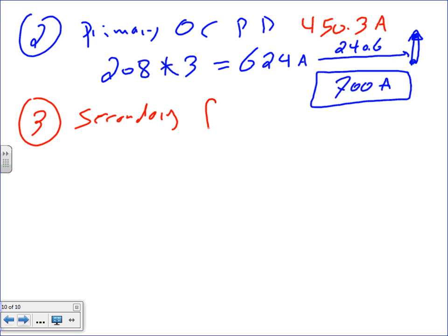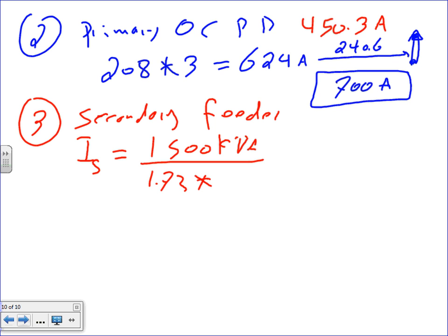Okay, let's go to the secondary side. Secondary feeder. For the secondary feeder, guys, I secondary equals 1500 kVA divided by 1.73 times the voltage. What voltage on the secondary side? 480. Yeah, 480. So if you do the secondary, I came up with 1806 amps. This is 1806 amps. Did you come up with something different?